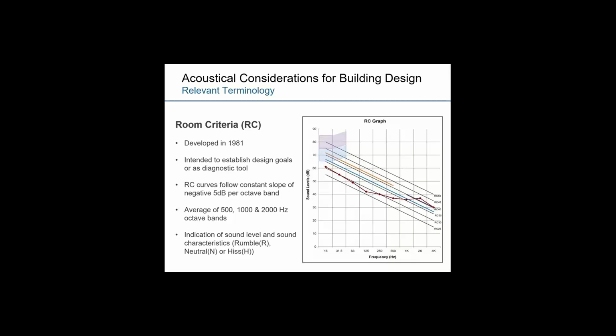RC is another type of criteria that's primarily used for referring to indoor spaces and what the sound level in that space would be. Used as both a design tool and a diagnostic tool, it's similar to NC in that you plot your representative sound pressure levels, and then through some averaging, you can understand if there is some indication of the spectrum of sound, whether it's a rumble, a neutral sounding spectrum, or a hiss. Again, like I mentioned earlier, low frequency dominant, mid frequency range, or high frequency. And you can see on the curves here and the color coding whether it's a rumble, a hiss, or a neutral sounding spectrum, which can be very beneficial.